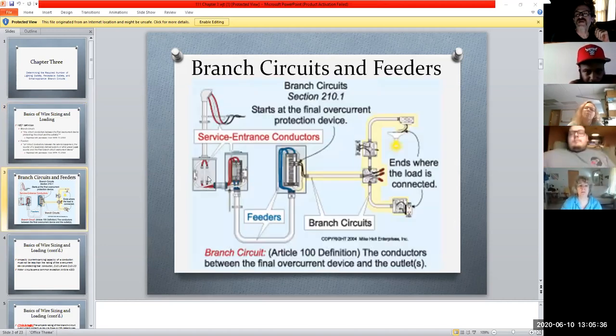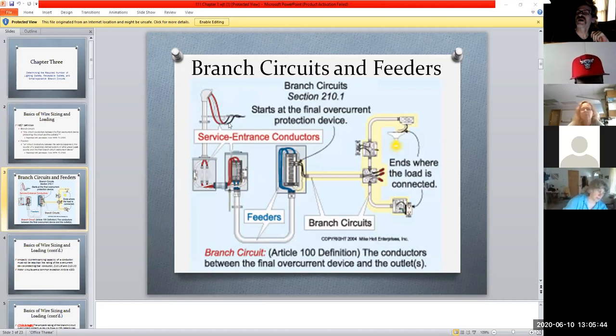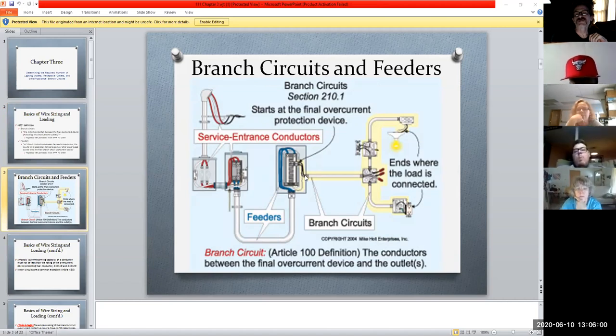So when we look at a pictorial of it, here we have basically the mast up on the outside of the house being fed in by the power company. It comes in and there's the meter box being fed into some type of fuse box here, coming into my main service panel. This is where I'm going to have the circuit breakers. Now from the circuit breakers, I feed what's considered a branch circuit.